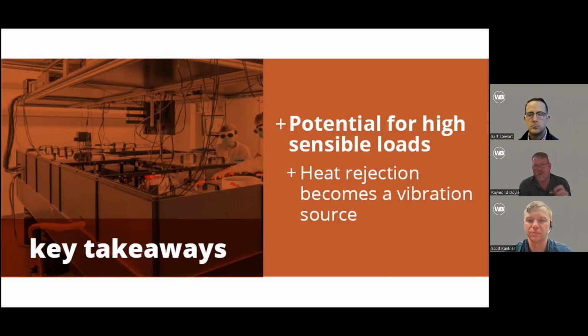One thing I'll add on sensible heat gains: in some of these spaces, Scott talked about photonics and optics. There's a key point here about calibration, and calibration based on airflow and changes in temperature and humidity. If you have a rate of change of temperature or humidity that happens too quickly, that can disrupt the calibration of the optics and equipment inside the space, and then you have to restart your whole experiment. So stable control of HVAC to meet the needs of this high sensible load is equally important.